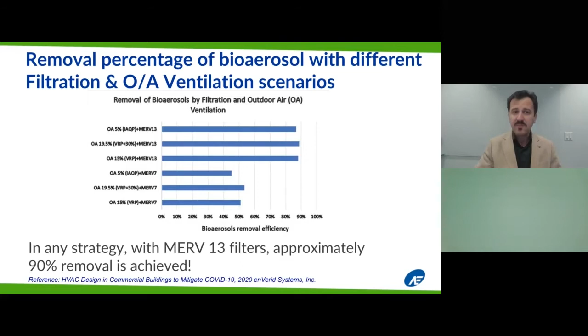Now, I spoke about filtration and ventilation and their impacts on removal of bioaerosols. However, here we want to compare the two methods that we have discussed so far. On this chart, you will see three different scenarios for outside air, starting from 5% outside air all the way to 19.5%, and with two different types of filtration. As you can see, in any strategy with MERV-13 filters, we can achieve approximately 90% removal, which is great. So this tells us that proper filtration is a much more effective way of removing bioaerosols from indoor air compared to outside air ventilation.